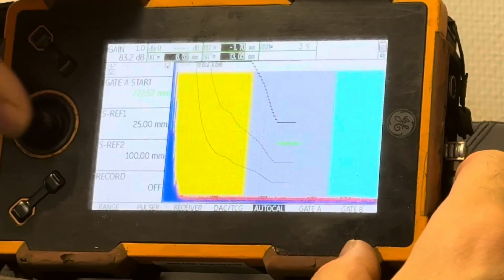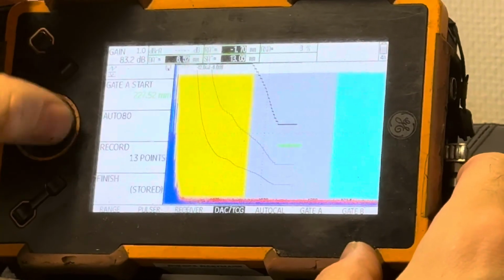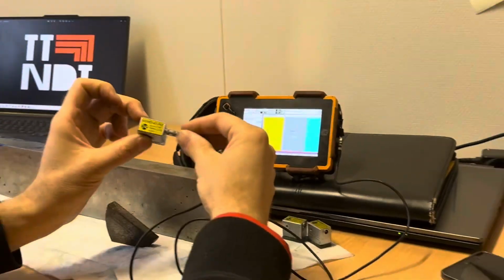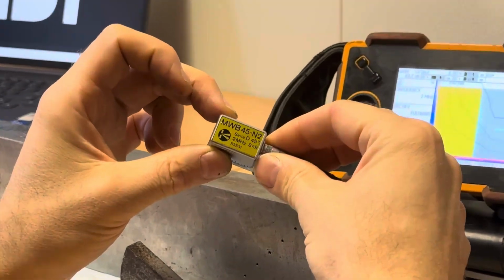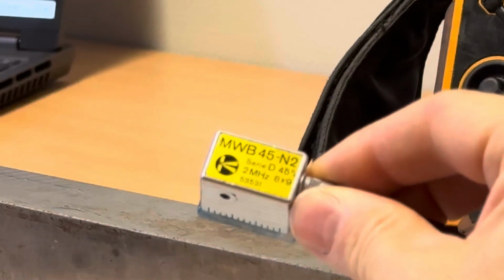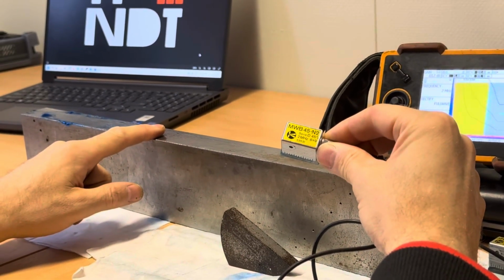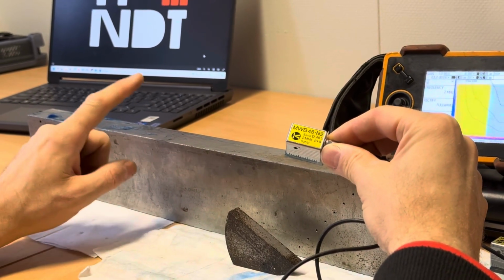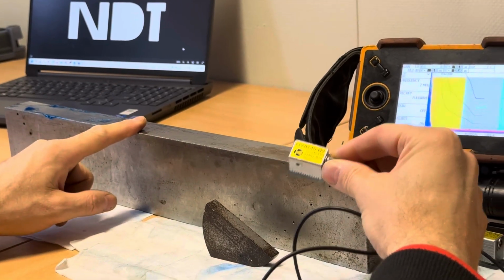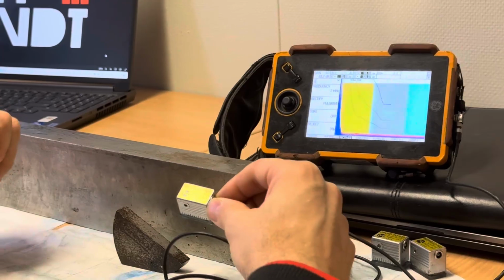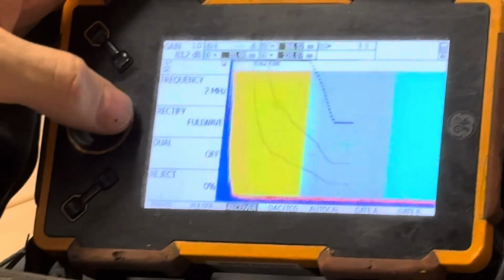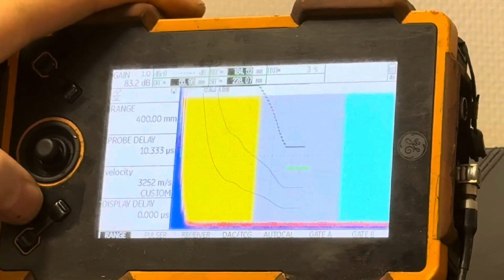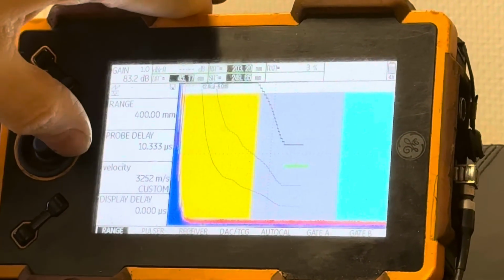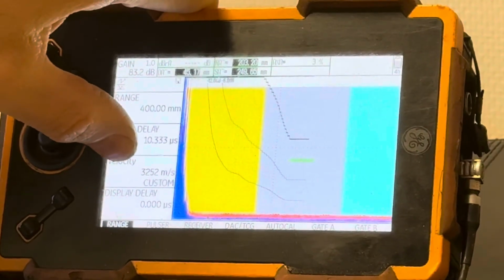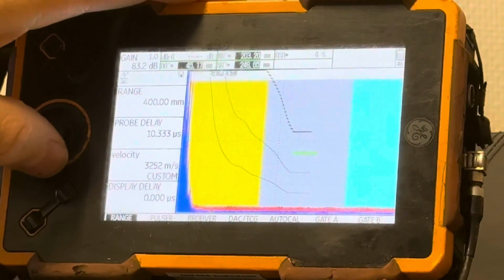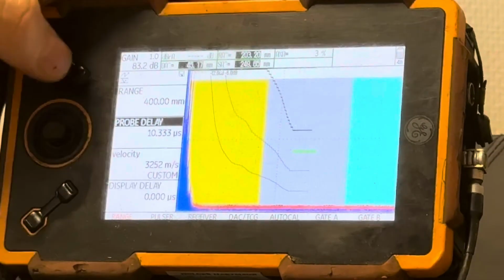Double check to make sure that it's set to 2 MHz. Since the probe is large, 2 MHz, we measure a greater thickness of metal. At this moment, we are calibrating on blocks with a block height of 85 millimeters, and the length is almost half a meter. So next we check that it's 2 MHz and we look to make sure the hairlines are there. Our estimated speed was about 3,250, with the probe delay being around 10 microseconds.